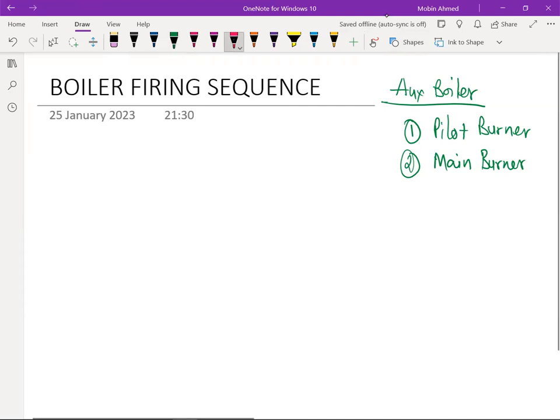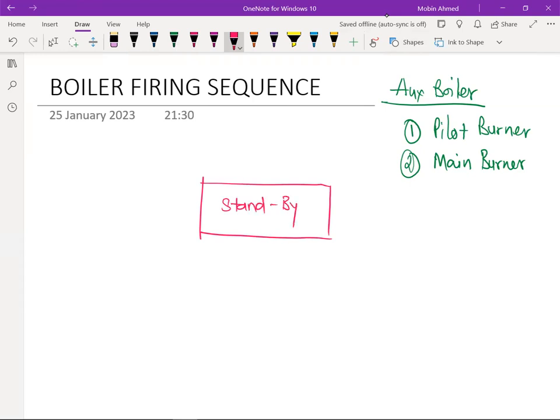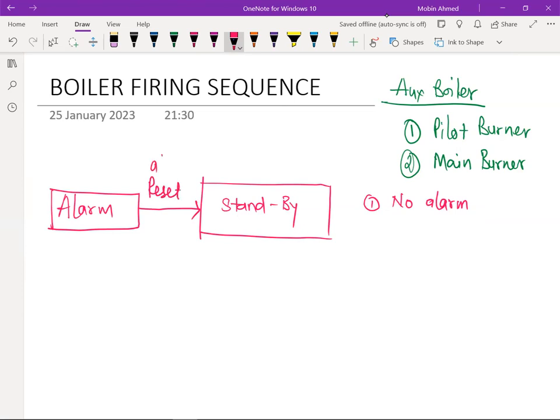So the firing sequence starts with the standby. The system should be in standby. Standby means no alarm, any type of alarm is not there. Okay. Now, suppose it is in the alarm condition, it will never be in the standby. So when it is in the alarm condition, you need to reset it. After reset, it is supposed to go to the standby.